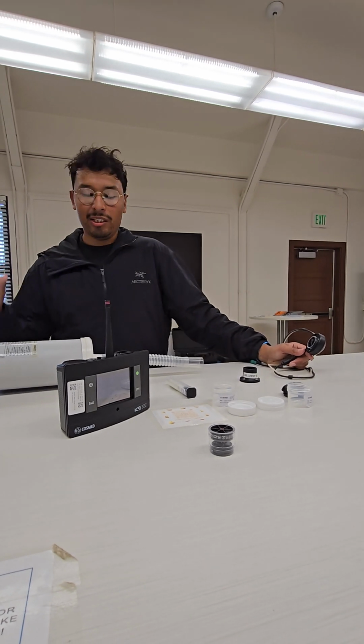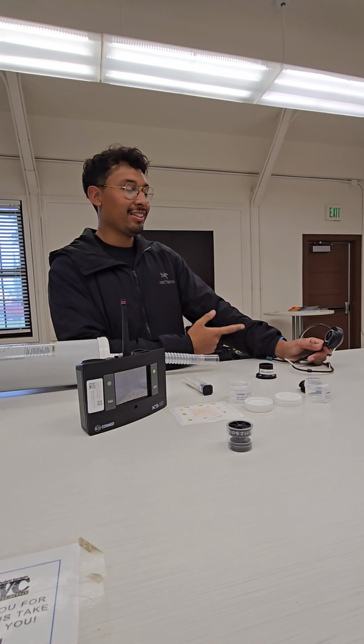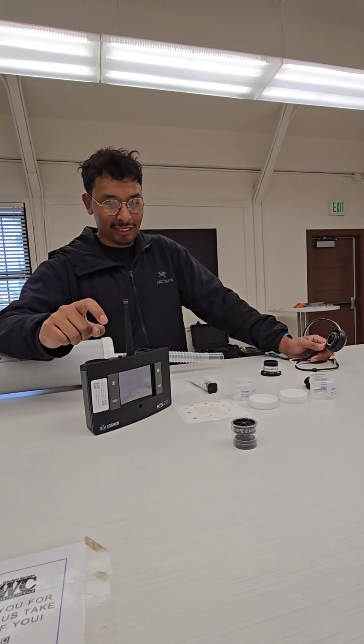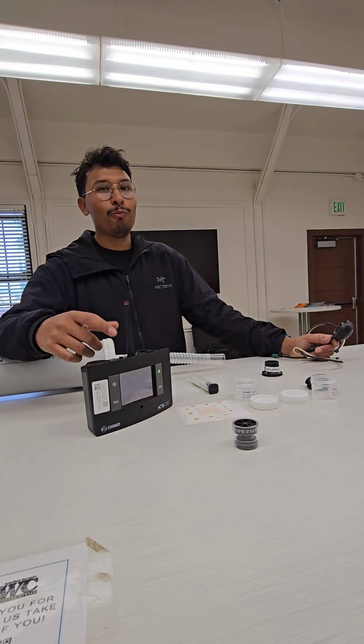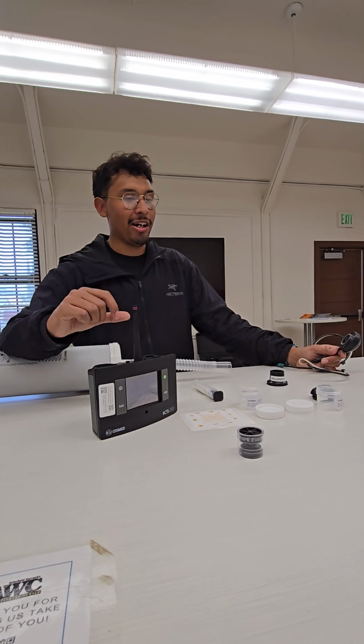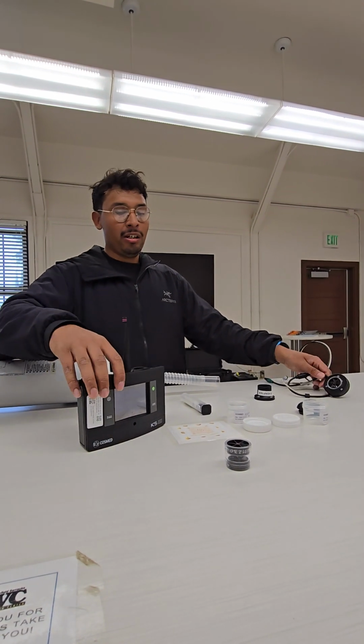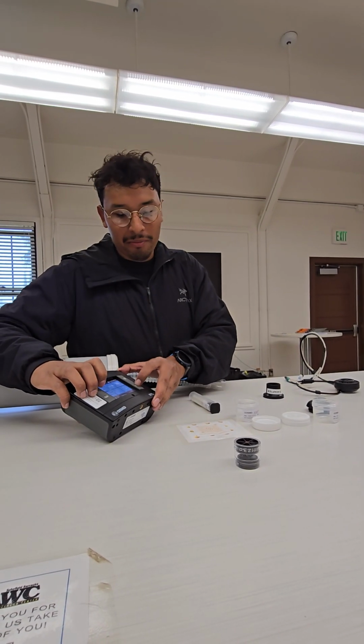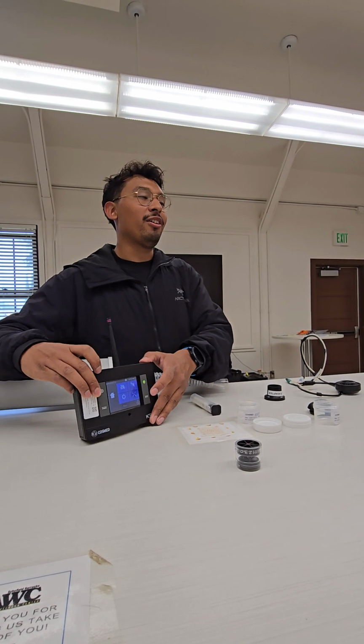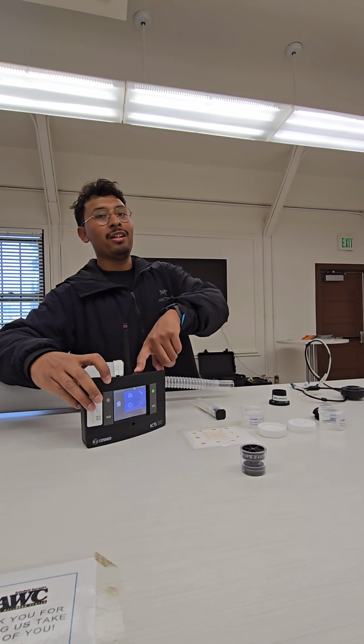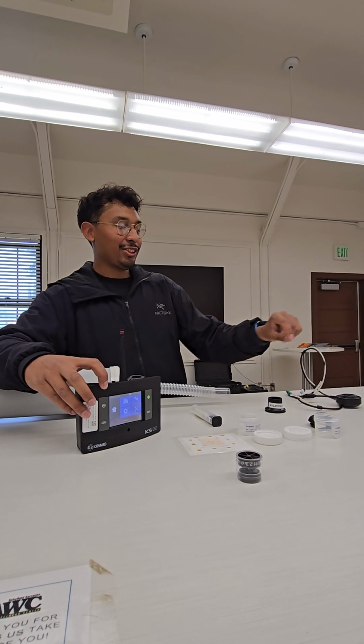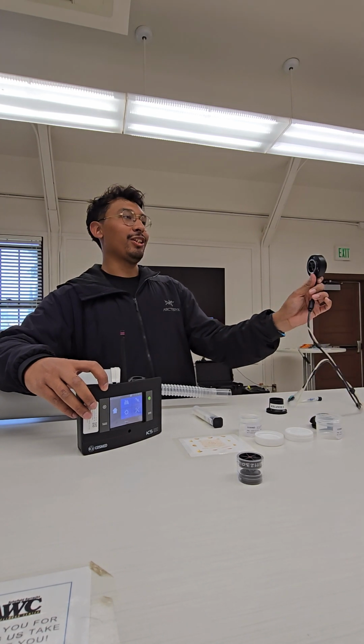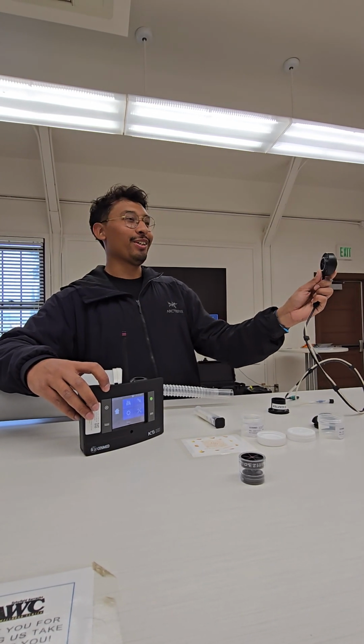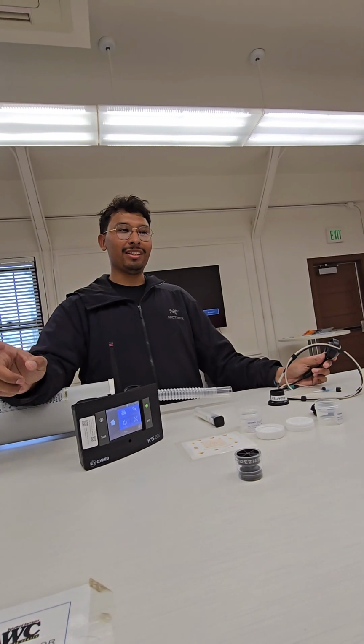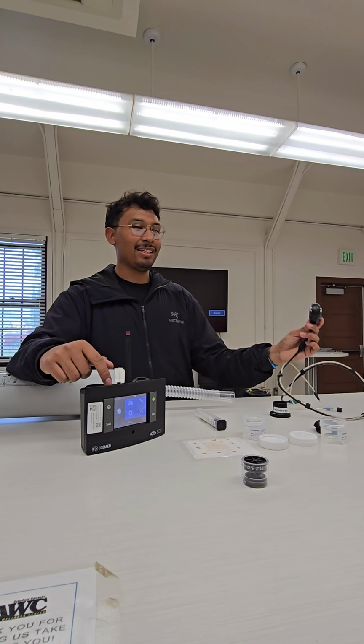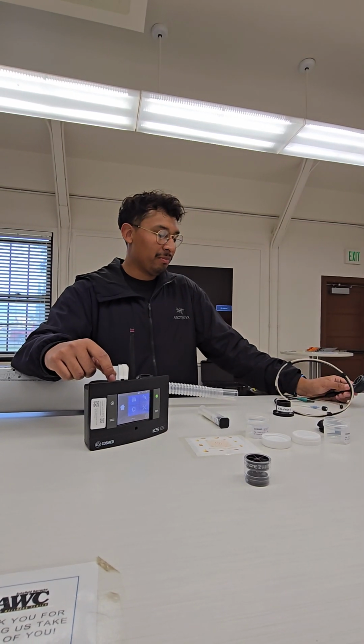So we use a 3-liter syringe to pump 3 liters of air through the turbine. The system should recognize that it's getting 3 liters. It's usually like 2.9899, something like that, or right above. But if there's a small error, the system will correct for it. And that's important because you want to make sure that you're doing the calibration for this one turbine, and then you test with that one turbine. You don't want to do a calibration with this turbine and then test with a different turbine, because the system is recognizing the error of that one turbine.